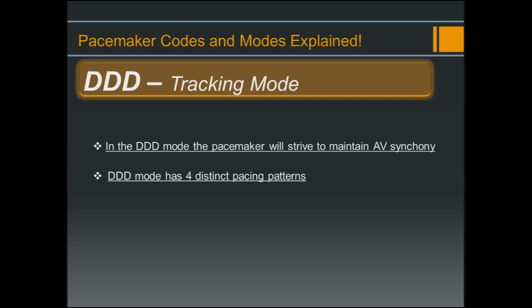Another thing to note is that with DDD pacing mode, there are four distinct pacing patterns that you could potentially see at any time, depending on the patient's intrinsic conduction. These patterns are: A sense/V sense, A sense/V pace (also known as P-wave tracking), A pace/V sense, and A pace/V pace.